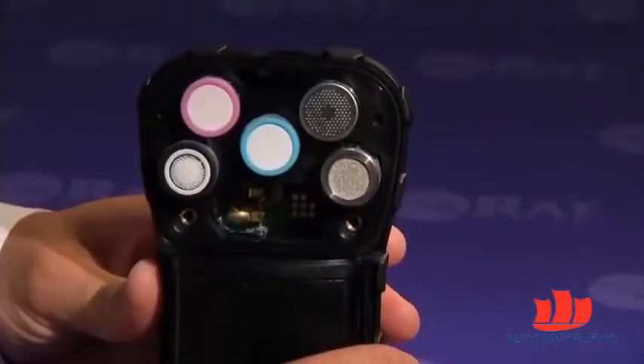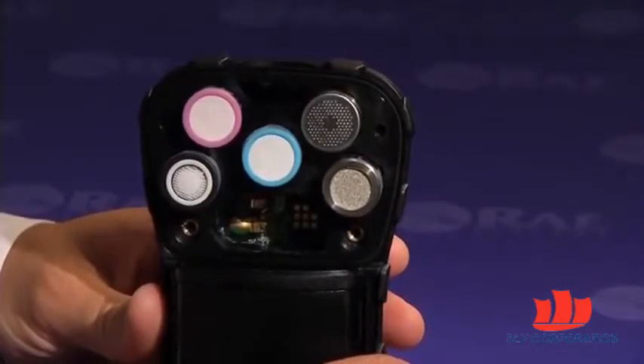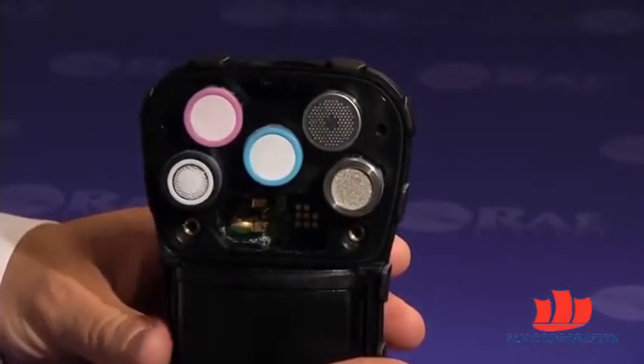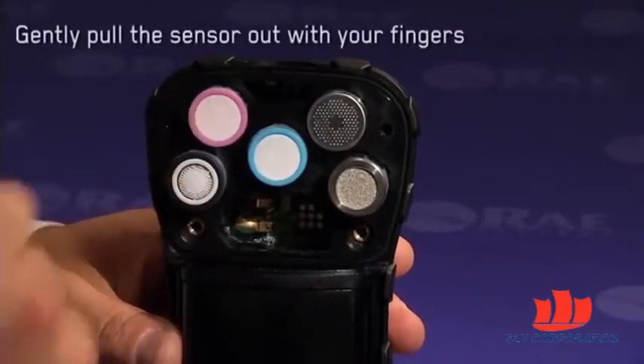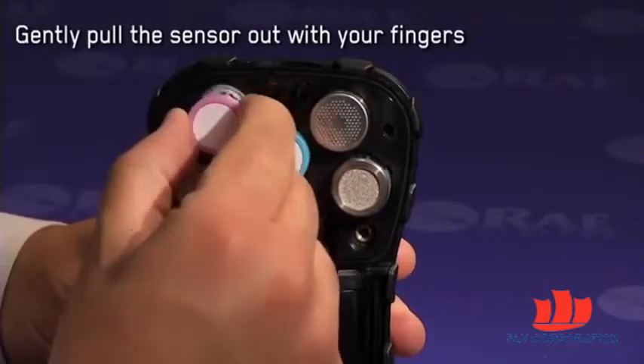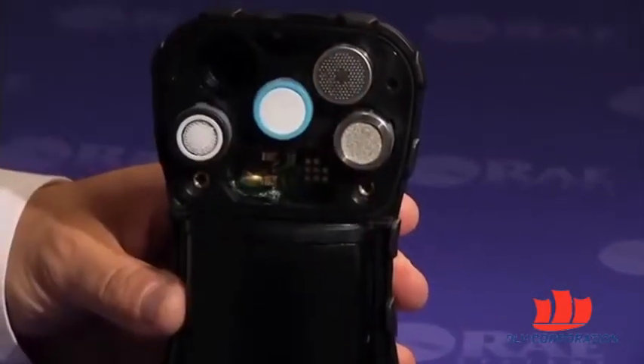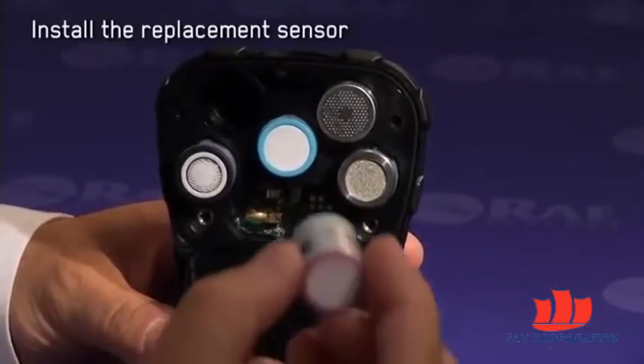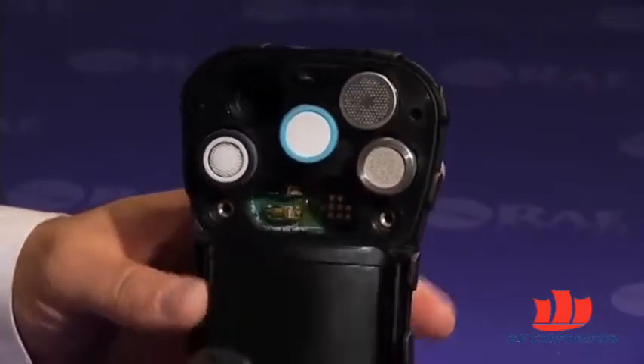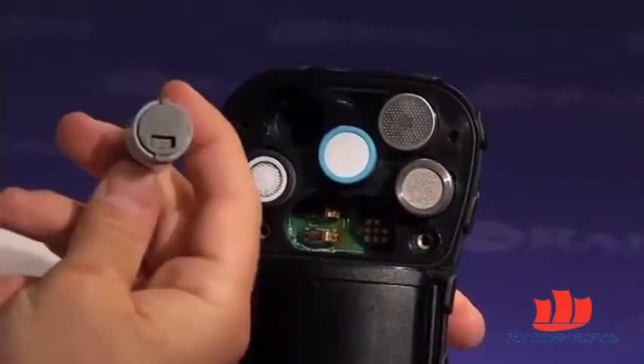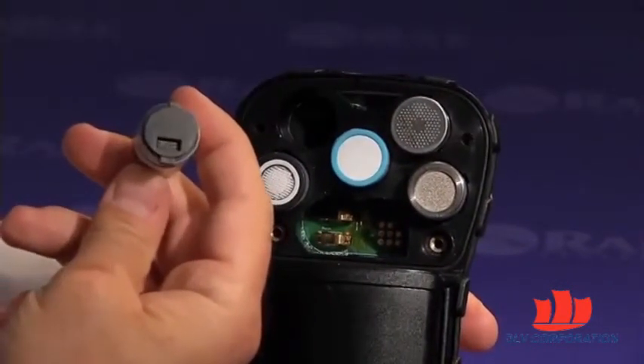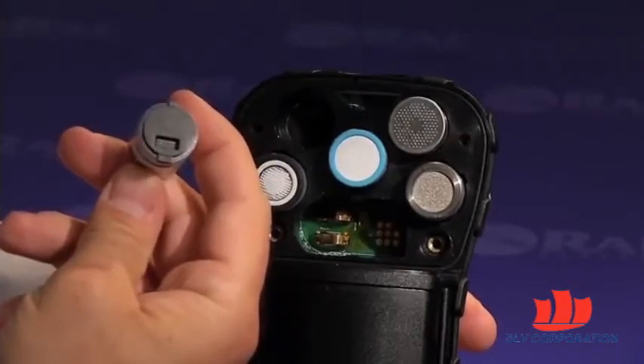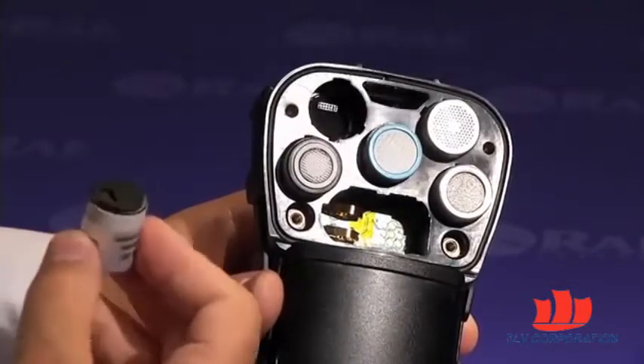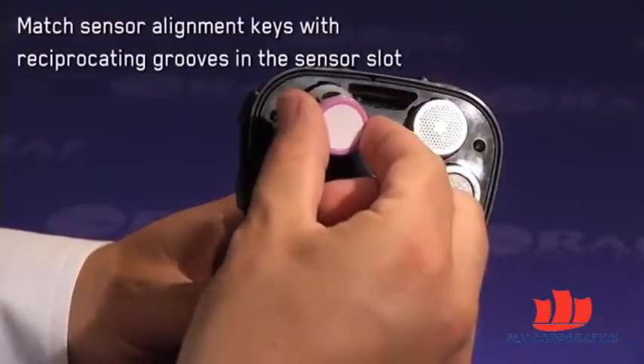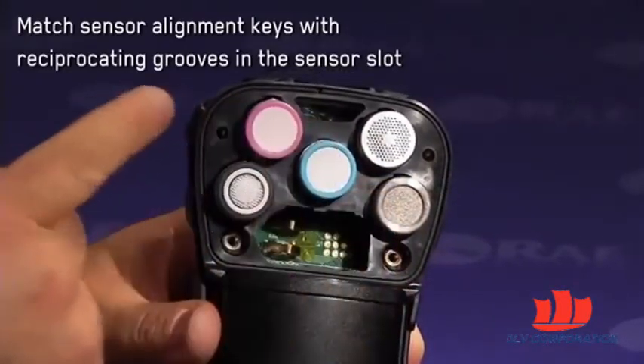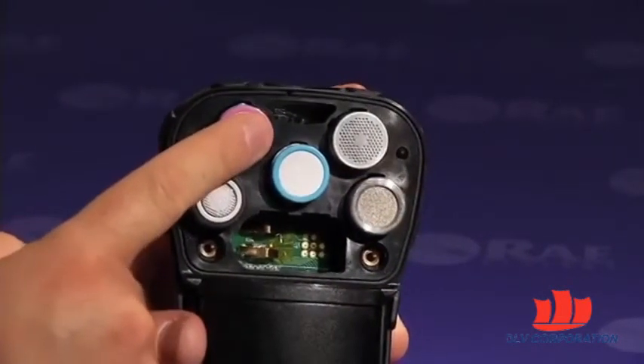Here you can see all the 5 sensors neatly seated in the respective sensor slots. Let's say I wanted to replace the CO sensor. So I would pull it out with my fingers carefully, remove the used sensor, and install a new one. Each sensor has keys on it to simplify the sensor insertion process. The sensor can go into the sensor slot only one way. Make sure you match the keys on the sensor with the openings in the sensor slot. Insert the sensor all the way in.